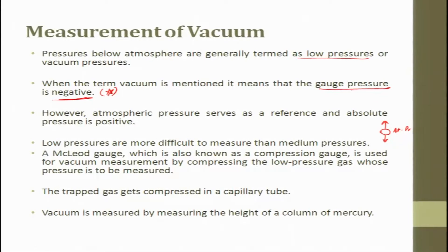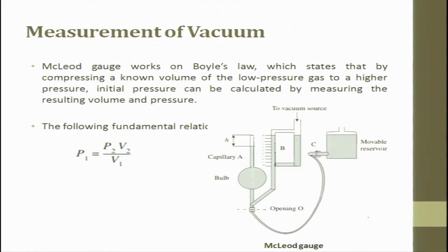The McLeod gauge, which is also known as a compression gauge, is used for vacuum measurement by compressing the low pressure gas whose pressure is to be measured. The trapped gas gets compressed in a capillary tube, and the vacuum is measured by measuring the height of the column of mercury. The setup has a bulb, a capillary which is attached, and a vacuum source which is attached.